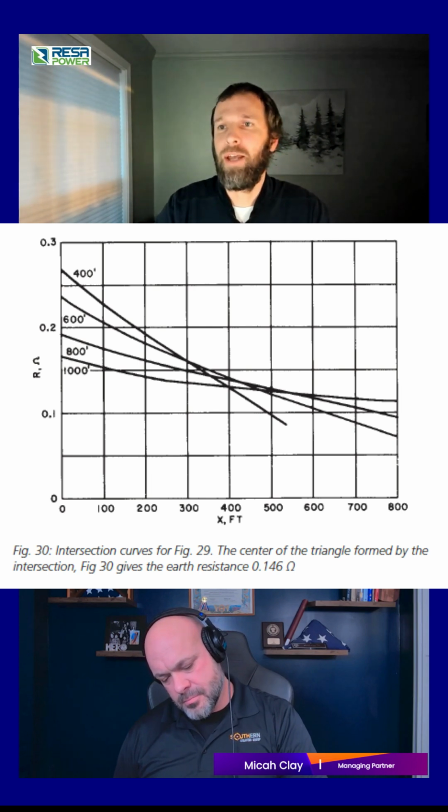You can reduce the diagonal length that you have to test instead of 10 times. You can reduce it down to 3 shots now. You have to do 3 tests, but now it's 2 times, 4 times, and 6 times. So it's much more manageable on larger grids. That's a cool trick that you can do, but you have to seriously read the literature and perform those calculations right, or you're going to have wrong numbers every time.